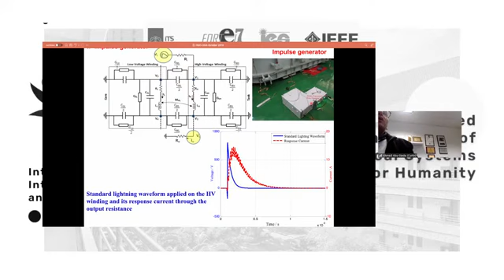Some other people asked: what if, during transformer operation, I connect an impulse generator? I only need maybe 1 kilovolt or 500 volts for a few microseconds. Can I connect it to an operating transformer, for each phase, and plot the FRA? So they connected an impulse signal through an impulse generator and measured the impedance, or admittance, or transfer function against frequency. We also did some of this work using a pulse generator connected to the transformer, and found that yes, it can plot the FRA. What you see here is what we did using the impulse generator compared to the signature from the small device offline test—they are identical.